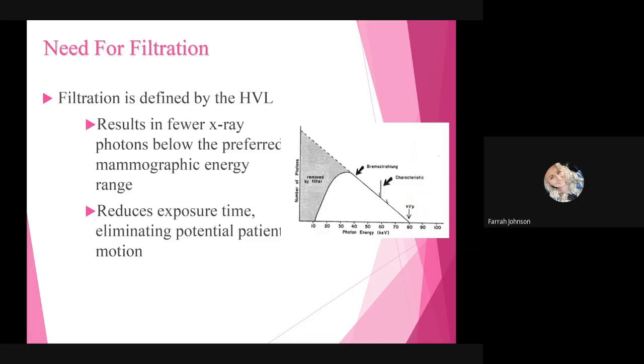So what is the need for filtration? Filtration is going to be defined by the half value layer of your machine. Half value layer is simply how many millimeters of aluminum it takes to reduce your X-ray exposure by half. So the higher the half value layer, the higher the filtration. Filtration is going to result in fewer X-ray photons below the preferred mammographic energy range. It also reduces exposure time, which eliminates potential patient motion. Anytime you're using a filter, whether in mammography or even X-ray, there is a fine line between when filtration is helpful and when it can be used in excess and actually does us a disservice.